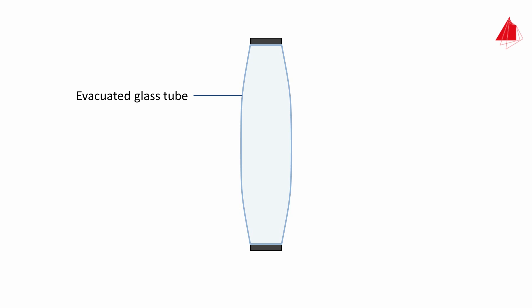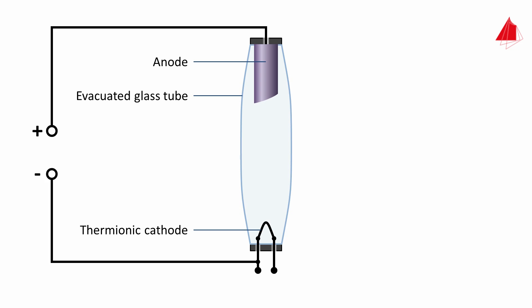But how are x-rays actually produced? They are generated in a so-called x-ray tube. To build an x-ray tube, first of all a thin-walled glass tube with a high vacuum within is needed. In the lower part of the tube, a V-shaped wire made of tungsten is positioned. This is the so-called thermionic cathode. A cylinder with an inclined end face is located in the upper part of the tube. This cylinder is the anode, made of a refractory metal that conducts heat well. From a high voltage source, the positive pole is connected to the anode and the negative pole to the thermionic cathode.